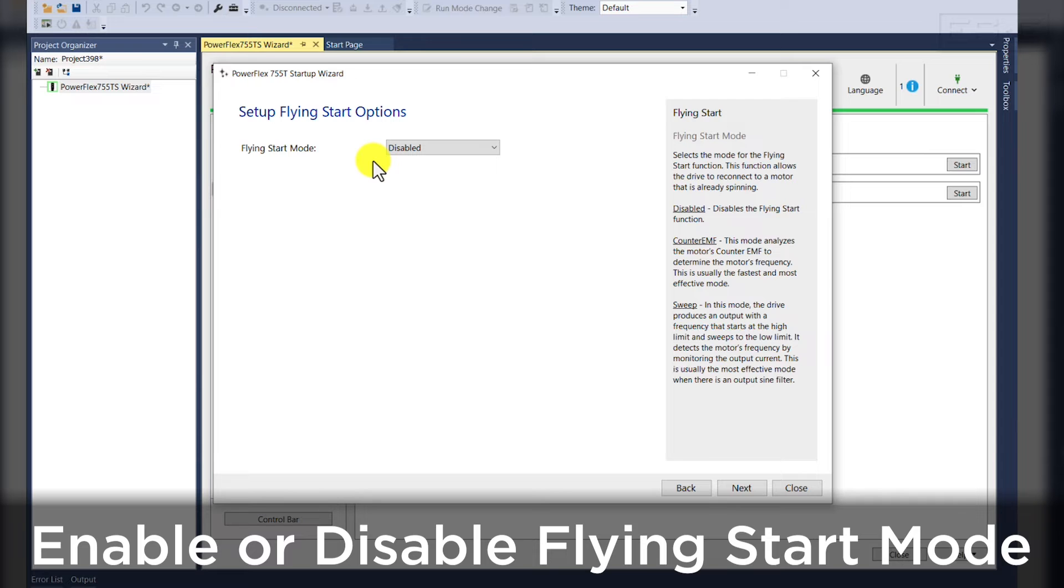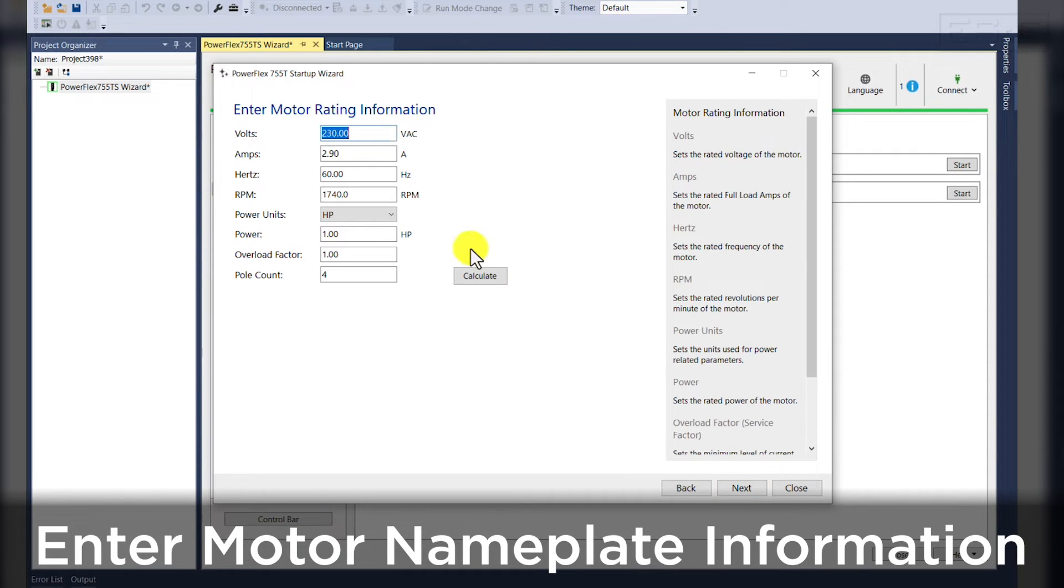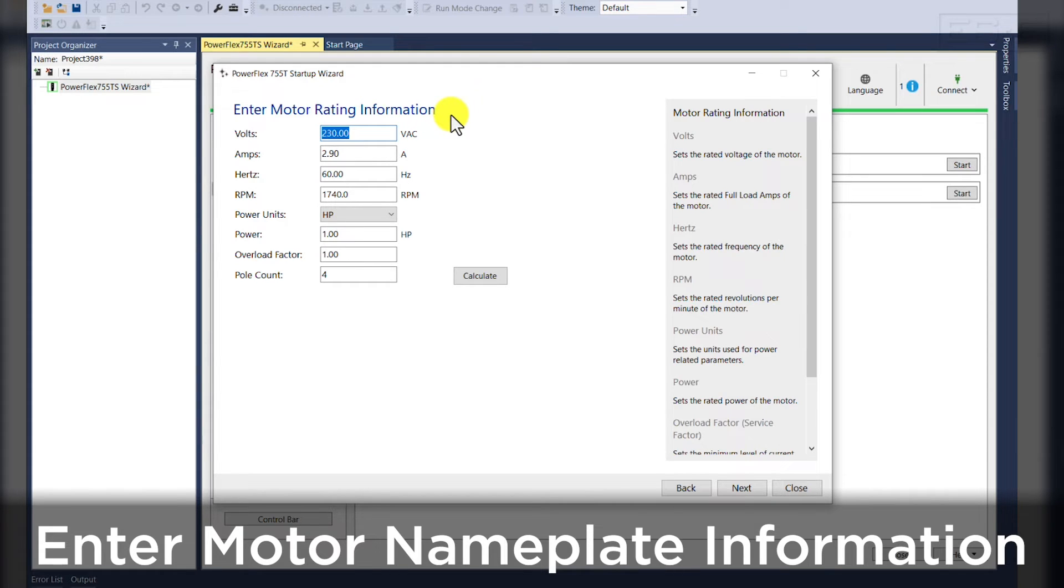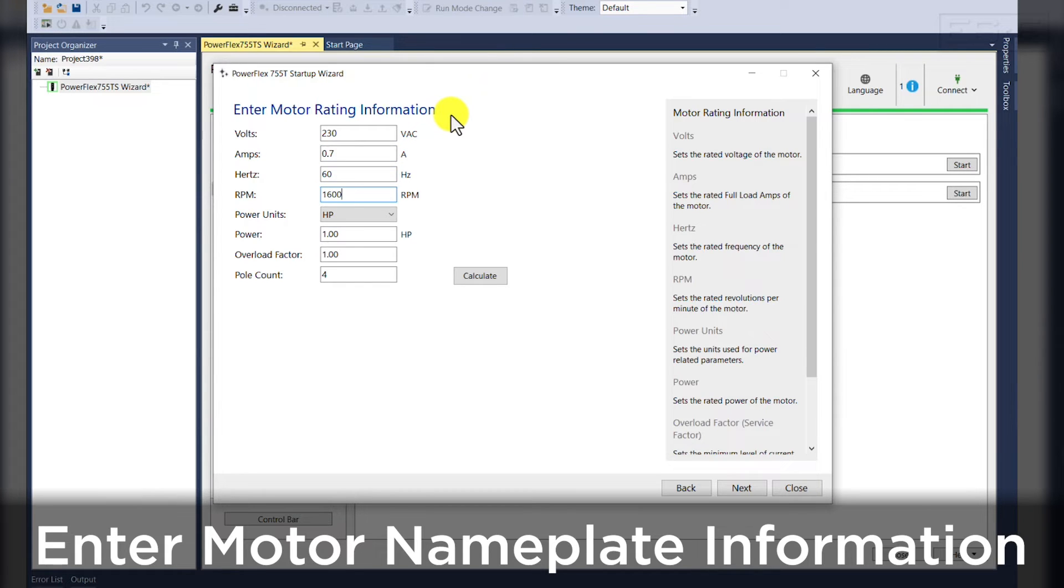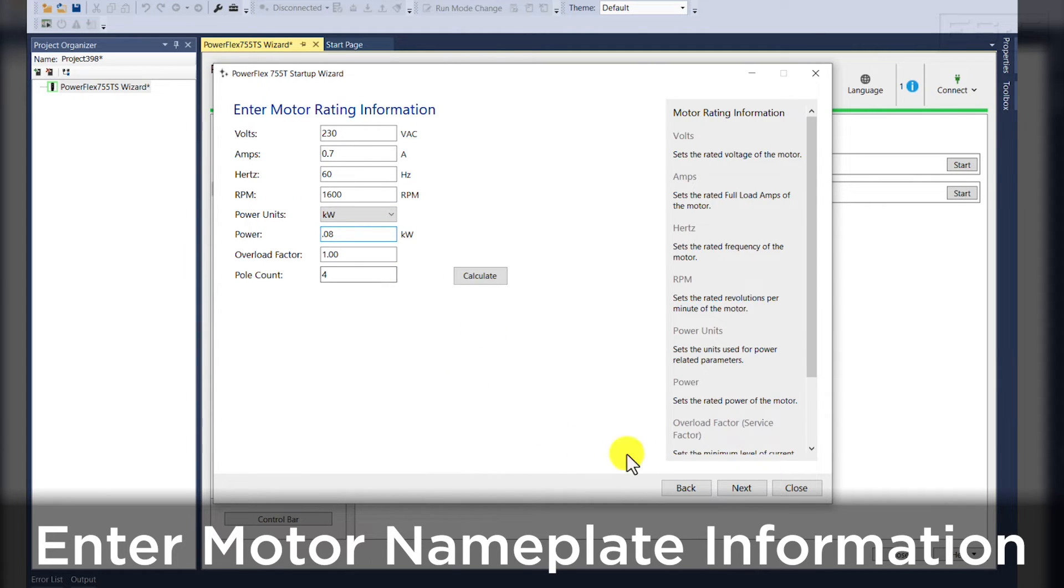Once we hit the next button, we will enable or disable flying start. You're then prompted for the motor nameplate information. In this exercise, we have a 230 VAC, 0.7 amp, 60 hertz, 1600 rotations per minute. Our power is in kilowatts and a four pole motor count.